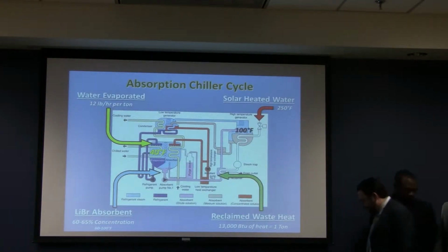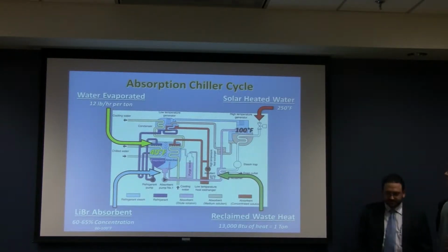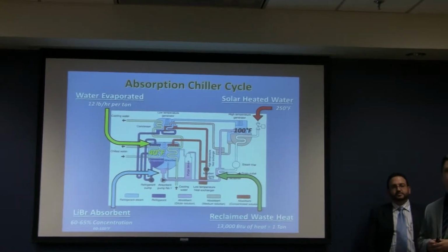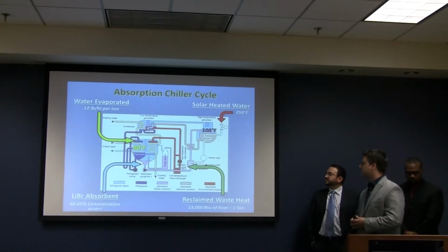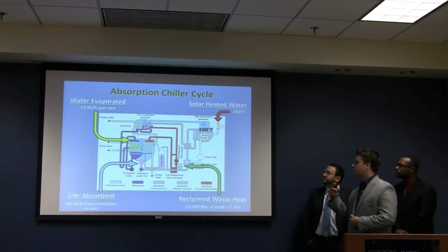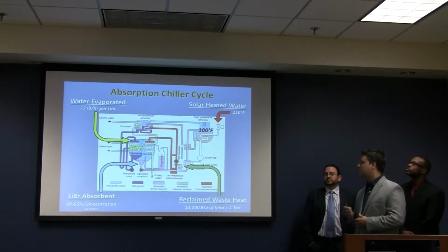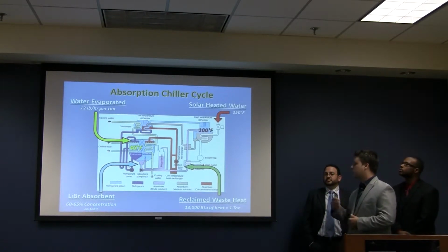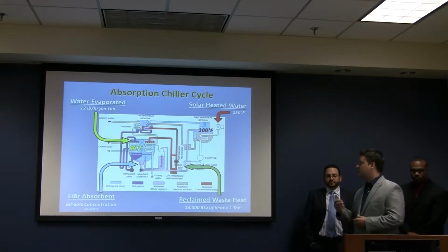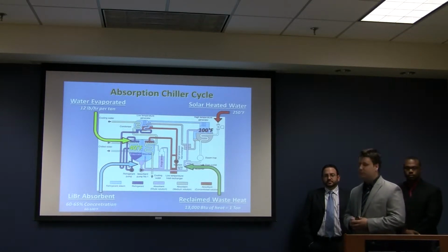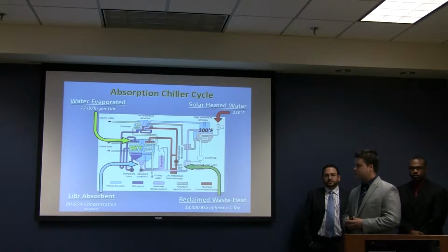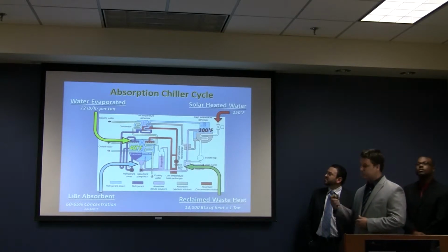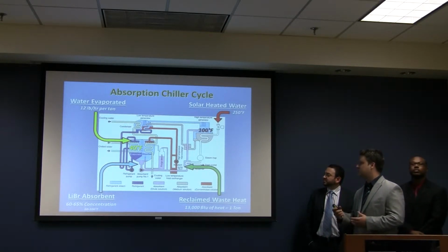The absorption chiller uses heat as power. By reducing the pressure in the system, we can boil the water at 40 degrees in the evaporator and 100 degrees in the generator. The hot water that we want to supply will be heated by the solar water heating up to 250 degrees, which will drive the generator. The water refrigerant in the system exchanges heat to produce chilled water.